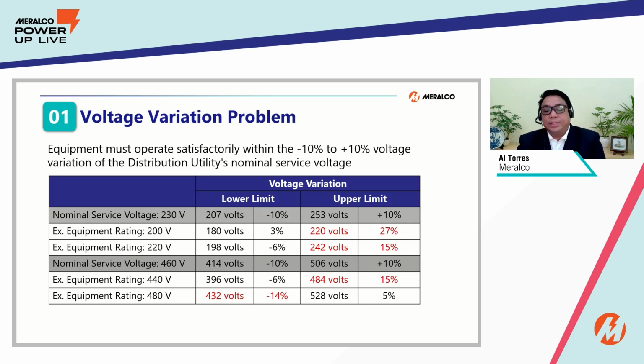Same with the supply voltage, equipment must operate satisfactorily within the plus minus 10% voltage variation of the distribution utility's nominal service voltage. However, the problem will arise if the supply and the equipment rating do not match. A common scenario is the use of 220 volts rated equipment on a 230 nominal service voltage. Also common in a manufacturing setup is the use of 440 volts rated equipment on a 460 volts nominal. Pagka hindi match yung equipment natin, very prone siya sa voltage variation problem.